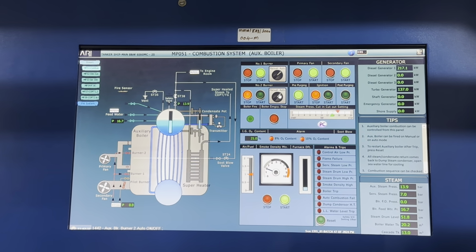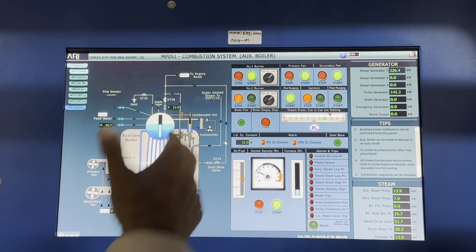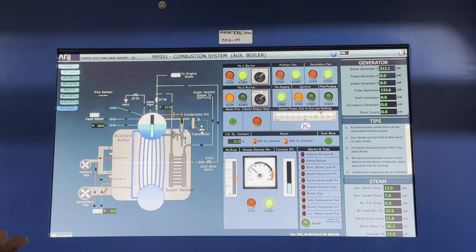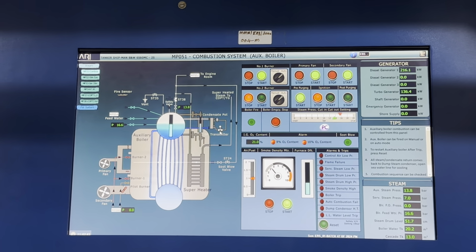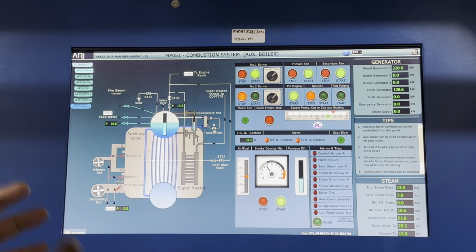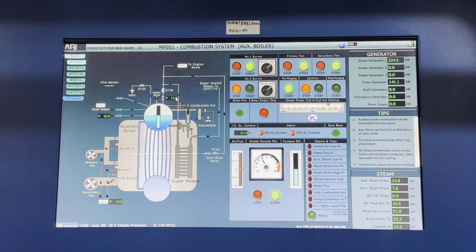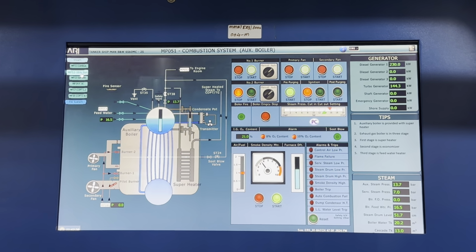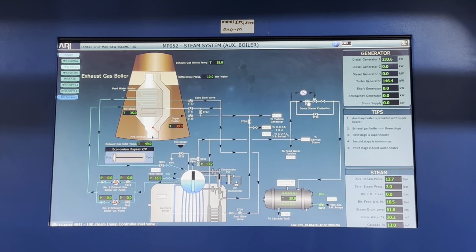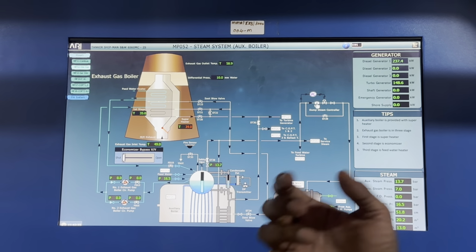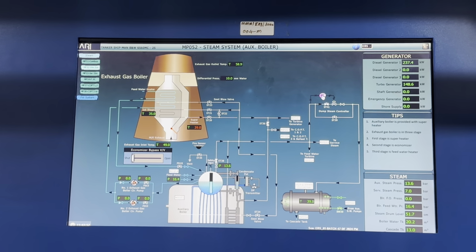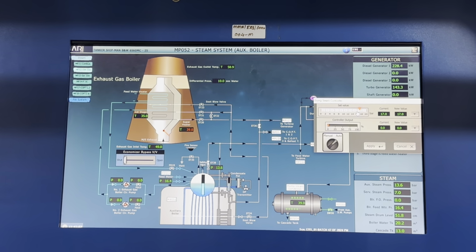Tell, na. Yes, put it manual. No, manual is manual, that is auto firing and all. Nothing like that. Increase the load. Load is the steam consumption. So the steam consumption, how can you increase? You have to go to your steam system, the dump valve, because the dump valve is set as open now. The dump valve is set at how much? 17. We can reduce. Yeah, set it at 16.